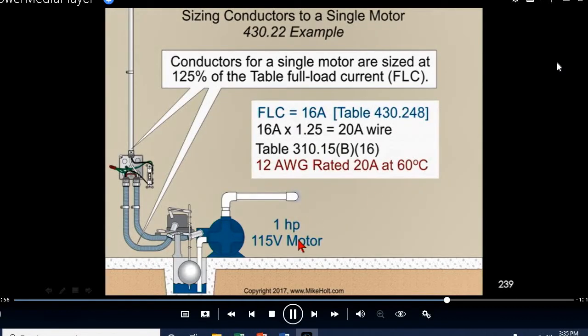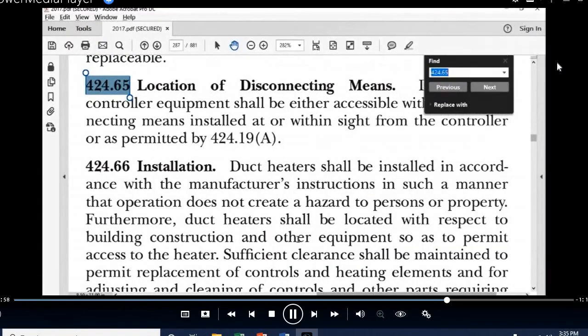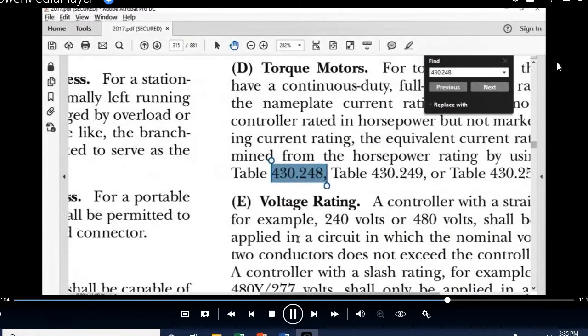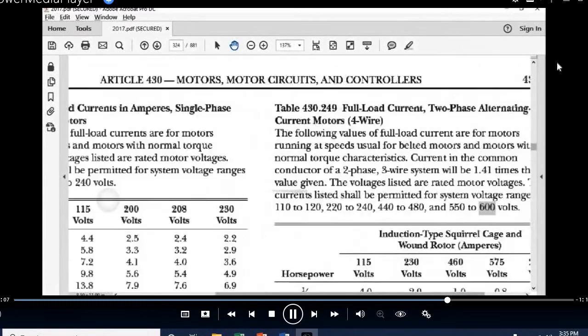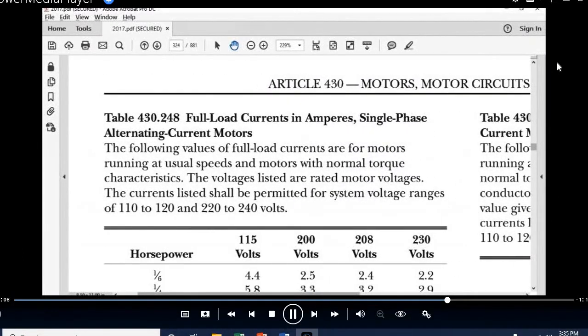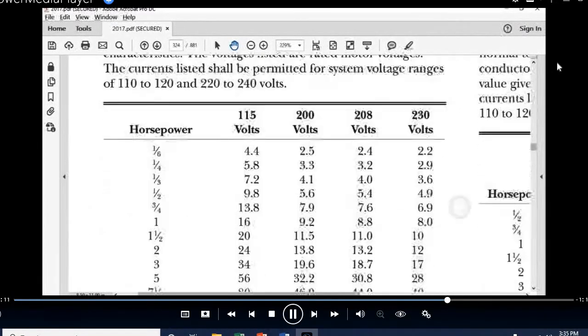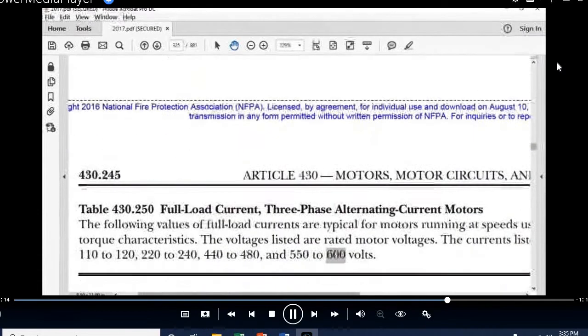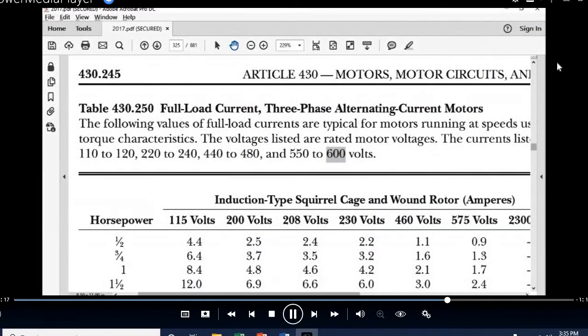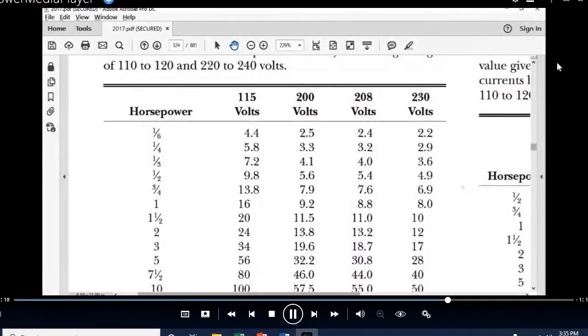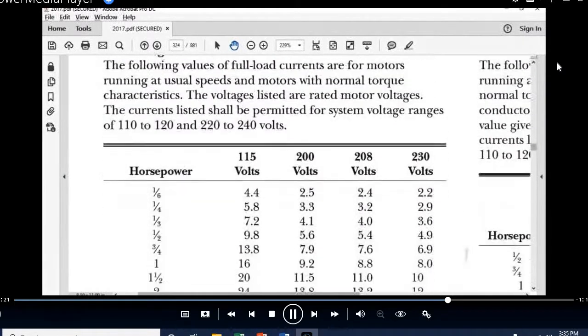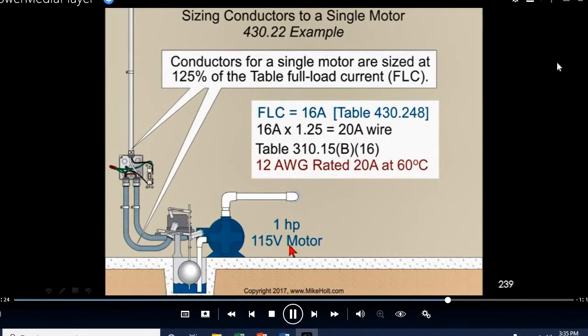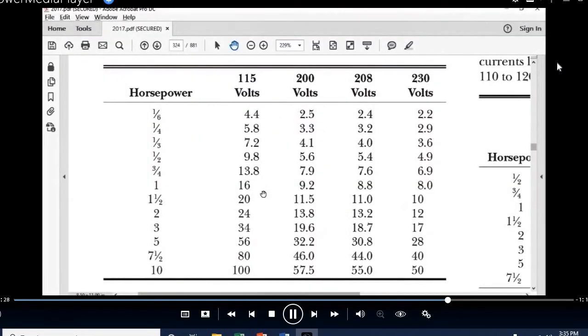Let's go to a 1 horsepower motor. So let's go to the code book, and that's going to be 430.248. And there's going to be a table there. But I found out you can also go to the motor rating and not get it, because that's where they get that rating from. And 250 is 3-phase. So using our example of single phase, 1 horsepower, 115. I like using the voltages that are going to be nameplate rather than nominal system voltages. 1 horsepower, 115 comes out to be 16 amps.